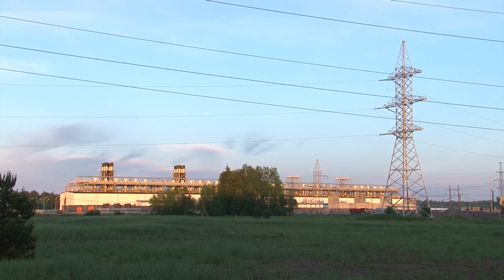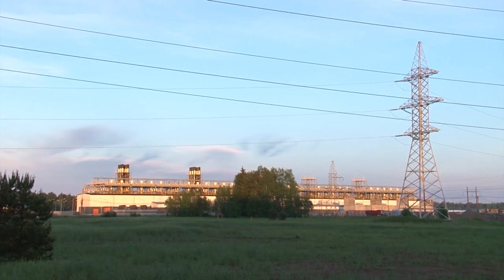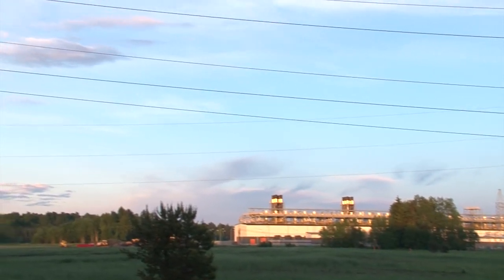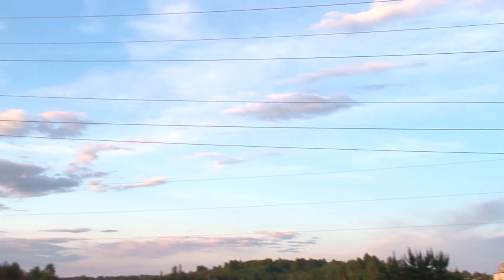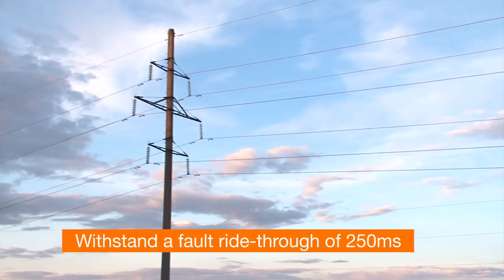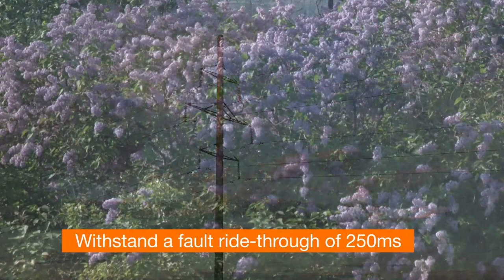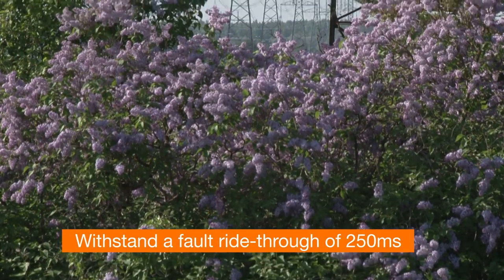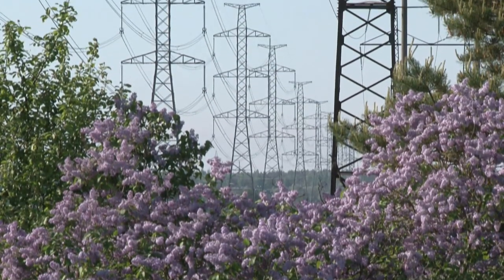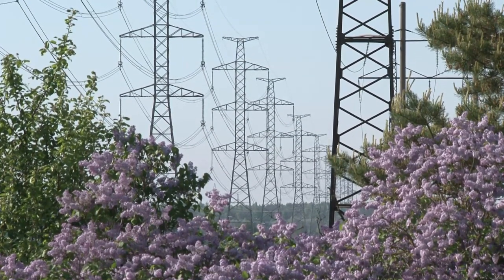Estonia's grid code requirements state that plants connected to the grid have to be capable of withstanding a fault ride-through, that is a period of lower grid voltage, of 250 milliseconds. This means a plant has to be able to withstand a disturbance of this duration without disconnecting from the grid.